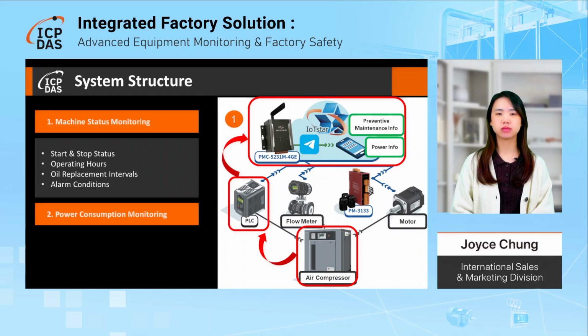ICP-DAS uses the PMC5231M4GE power meter concentrator to retrieve air compressor status data from the PLC and applies logical controls to set warning thresholds. The collected data includes the compressor start and stop status, operating hours, oil replacement intervals, and alarm conditions. When preset thresholds are reached, the PMC module automatically sends notifications via the Telegram app to maintenance personnel's mobile devices, enabling timely on-site maintenance for the air compressors.